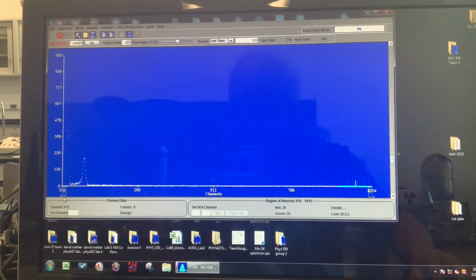It's occupying a lot of time here, so I'm just going to get rid of this, and I'll move my discriminator here, and notice that it no longer counts any pulses that have energies below the discriminator setting. So it's only building up count totals for the principal gamma of cadmium-109, which is at 88 keV. You would, again, get a really nice spectrum here, so you would measure for longer than what I am doing. We've set our gain so that we can see the lowest energy gamma and the highest energy gamma with a single set of gain settings.